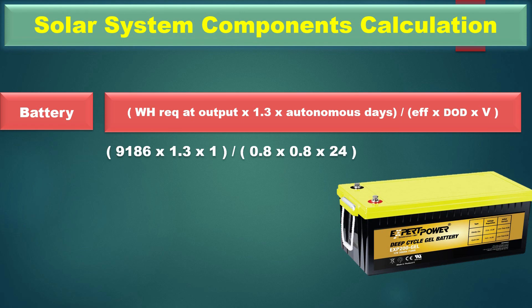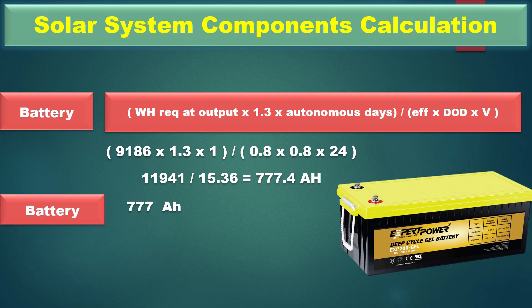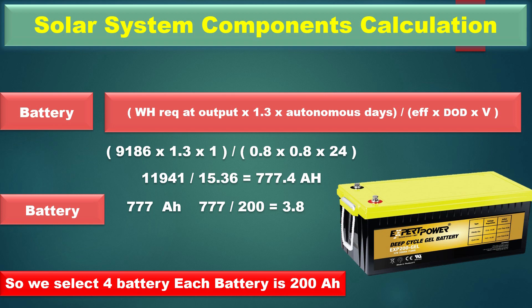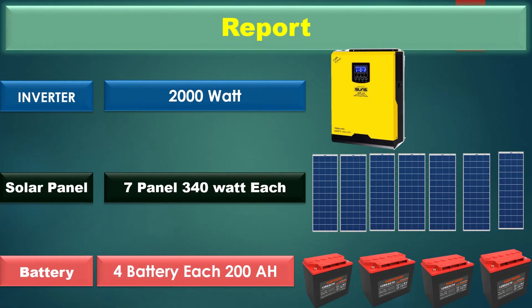Putting all the values into the battery formula: 9186 × 1.3 × 1, divided by 0.8 × 0.8 × 24, gives 11941 divided by 15.36, which equals 777 ampere-hours. We select a 200 ampere-hour battery available in the market: 777 divided by 200 equals approximately 4. So we select 4 batteries, each rated at 200 Ah.